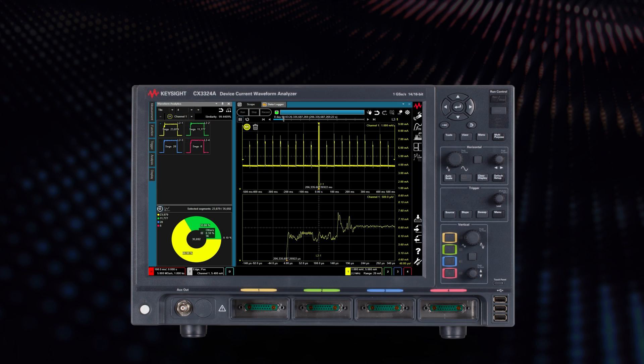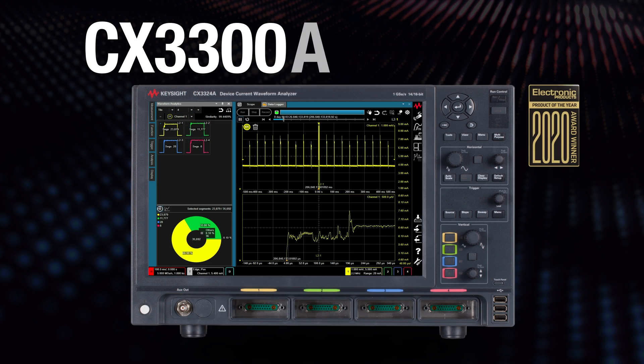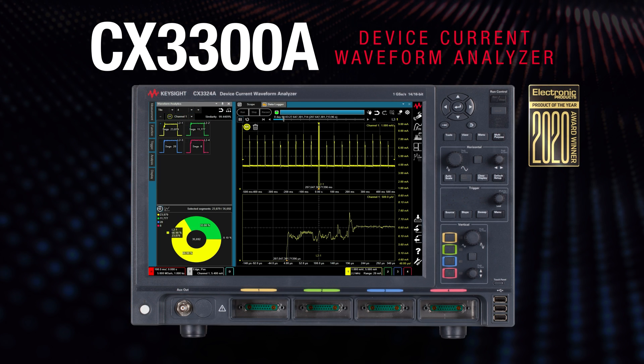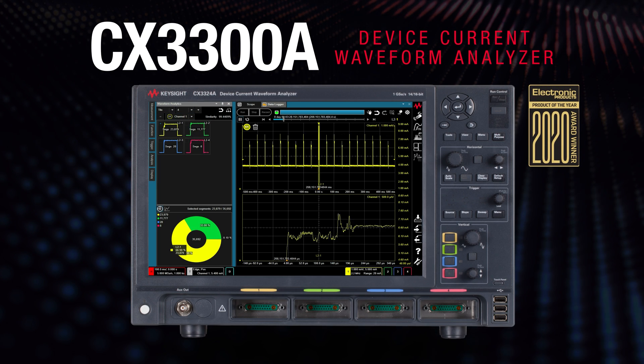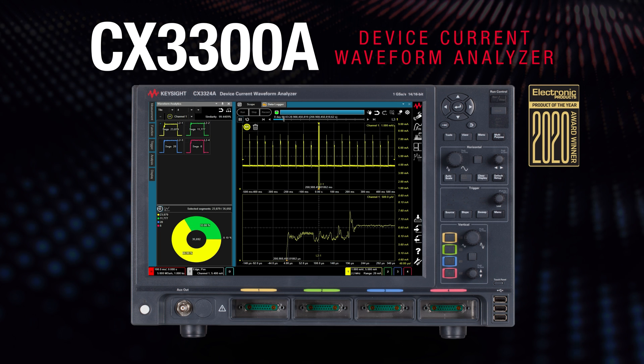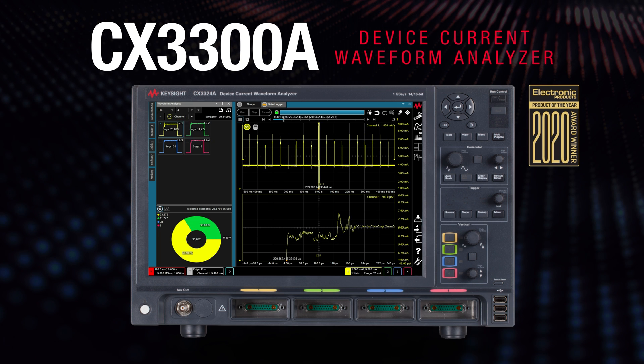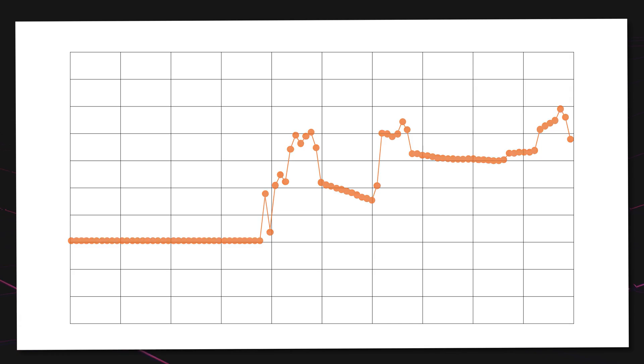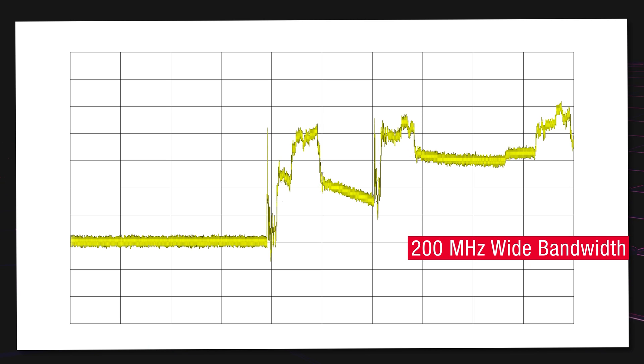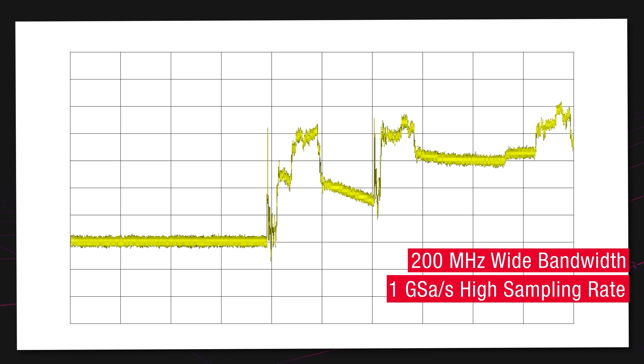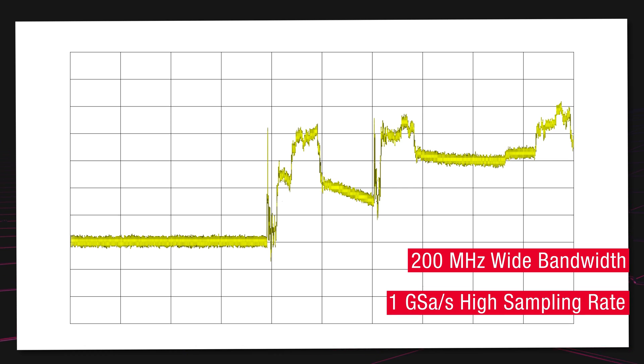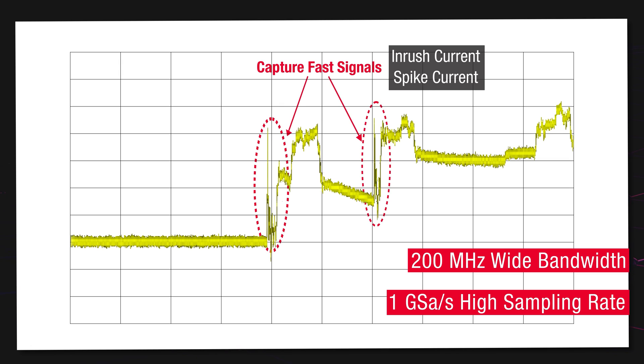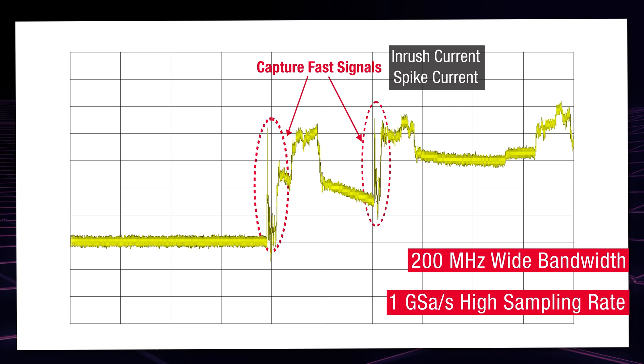The Keysight CX3300 device current waveform analyzer solves all of their challenges in a single unit. Its 200 MHz wide bandwidth and high sampling rate of 1 giga samples per second enable fast and transient signals to be captured and evaluated during the device operations.